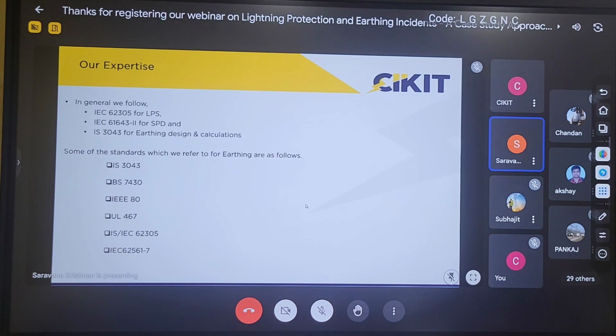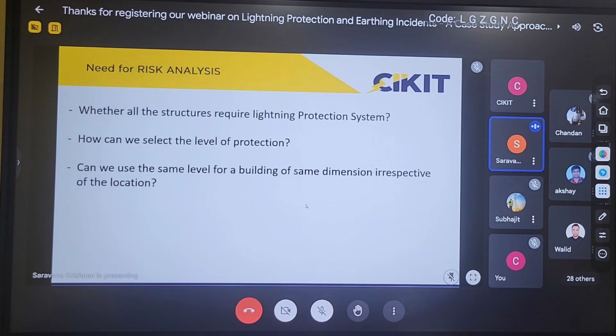If you take the lightning protection system, the risk analysis is considered as the first step of designing. So we cannot generally mention that all the buildings and structures require lightning protection system. First, we have to determine whether lightning protection system is actually required for the particular site or not. If lightning protection is required, then only we have to determine what will be the suitable level of protection for the particular site conditions. So the first step is to determine whether lightning protection is required for the site or not, and that can be determined by performing risk assessment calculations.